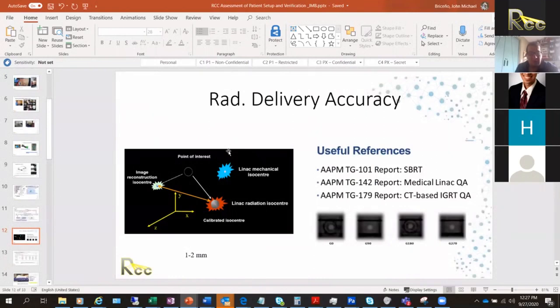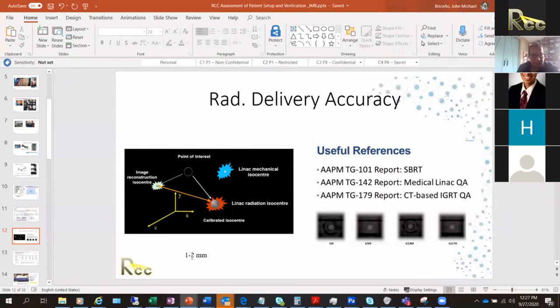We must ensure that the imaging isocenter, the mechanical isocenter, and the radiation isocenter of the LINAC are all within one to two millimeters of each other. For some machines this may not be achievable, but two millimeters should be attainable for most machines doing radiotherapy today.